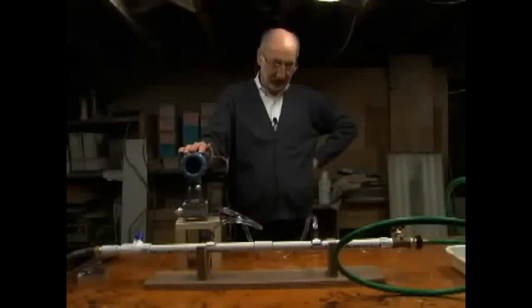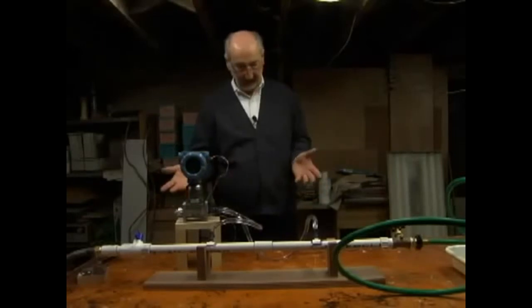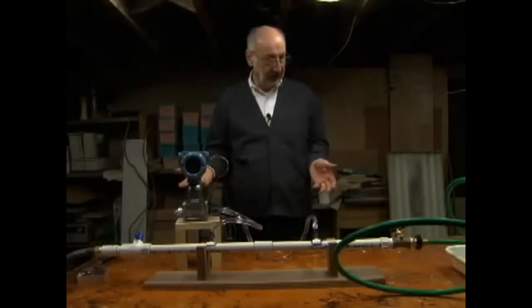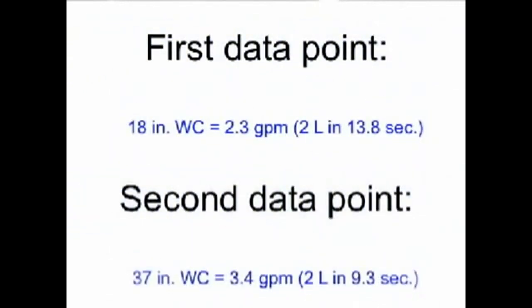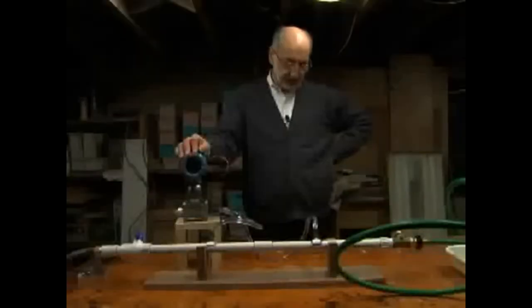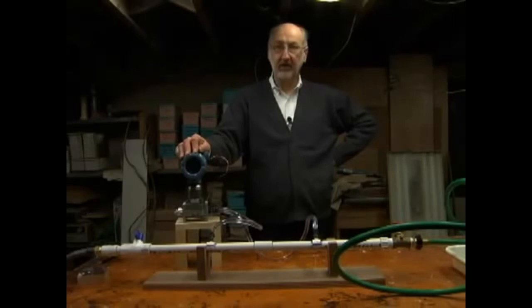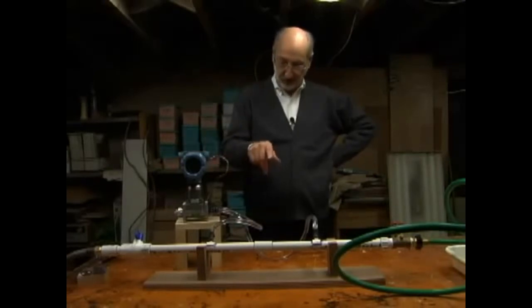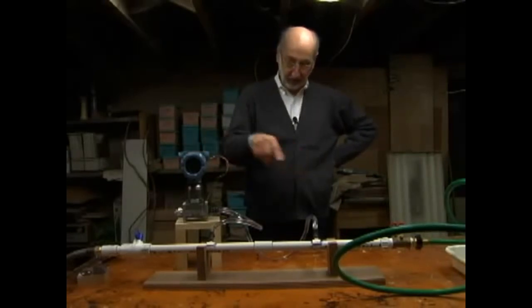Now if we want to do this in a real life situation, we could use this just the way it is. If you did enough tests and you got enough data points, you could create a graph which would give you a very close relationship between the differential pressure reading and the actual flow rate. There are also ways that you can do that through calculations. There is a website, eFunda Engineering Fundamentals, which gives you a very nice calculation based on the differential pressure and the various diameters that are involved.